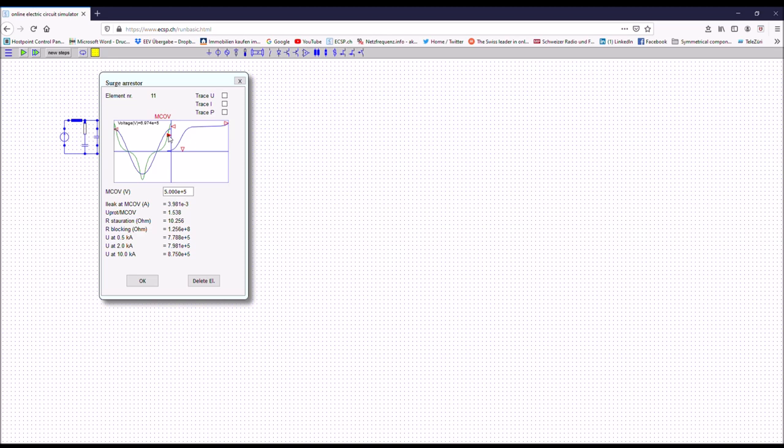The protection per maximum continuous operating voltage is here. So I reduce now this arrow here until I get around about 1.5. And then the settings should be okay.